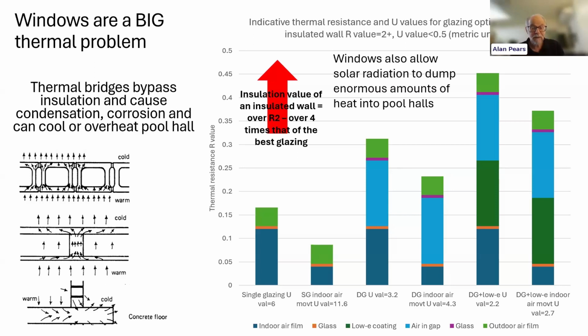The other big issue that keeps cropping up for me is this problem of thermal bridging. If you've got a metal frame, or even concrete, or a brick wall attached to a concrete slab, you can have a lot of heat bypassing your insulation systems. Where you've got thermal bridges, you tend to have cold surfaces that attract condensation problems, which will also add to maintenance issues.